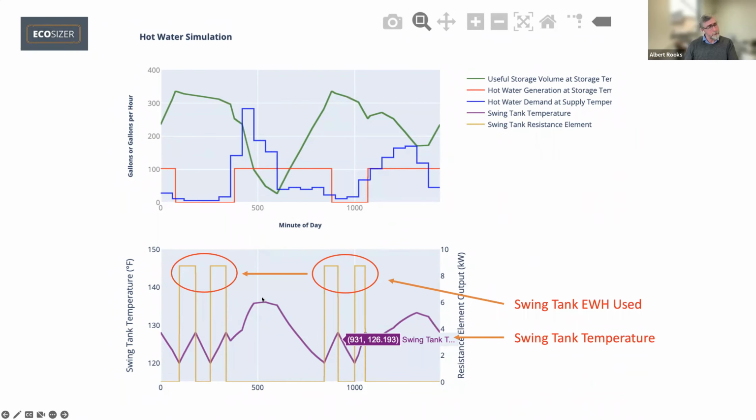So, that's like what we do with capacity and cycle time. If we've gained that all right, then all that works. And then we can see demand starts climbing up and supply starts going down. And then we can start seeing in the hot water generation, the red line. Essentially, the red line is watching our heat pump capacity, right? It's producing, it's filling primary storage, and then it stops producing. It's just resting. It's not functioning at all. So it's not burning any of those 16 hours in capacity. And then it turns back on, it runs for a while, and then turns back off, and then turns back on. Okay, so that's pretty simple.